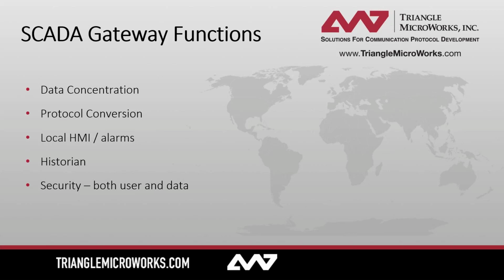Protocol conversion or protocol translation is used when you have a system that needs to communicate across multiple protocols. This is commonly used when a substation is communicating with one protocol, but the transmission may use a different protocol. Another common usage of this is when a system is being modernized or upgraded to newer technology, but legacy hardware is still required during normal operation.